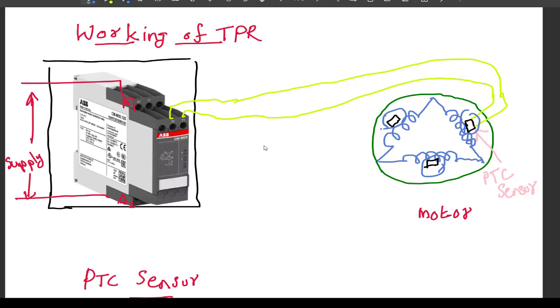You can only find it in bigger motors, like our ballast pump motors, the Hamworthy pack motors, electric motors like that. It helps in heavy duty starting and rapid cycling, and it is also useful in single phasing of the motor, of course. So if any of the windings gets a higher temperature, it will trip the motor. Okay, this is the working of the thermistor protection relay.